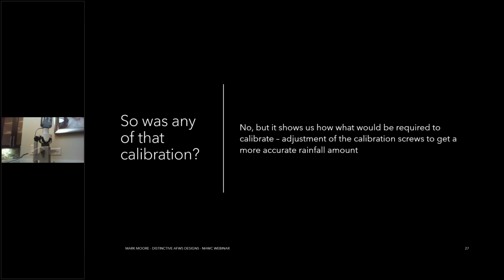Hey, Mark. Yeah. We have a question. Ben Pratt asks, what is the recommended frequency for both static and dynamic calibration? Yeah, thanks, Ben. So how often do we calibrate, specifically with tipping buckets? It somewhat depends on the needs and the goals of your system. But a general baseline is to do a static calibration anytime you bring a rain gauge into the test bench, and do dynamic calibrations in the field about every 6 months.